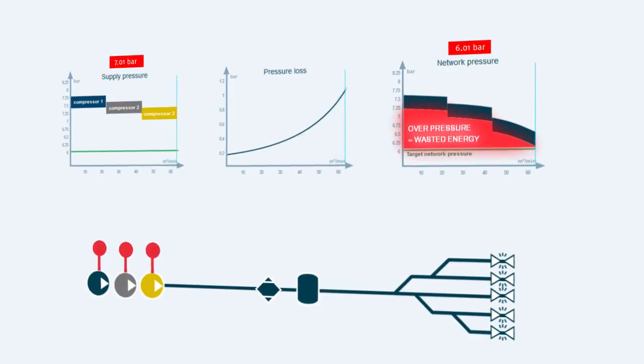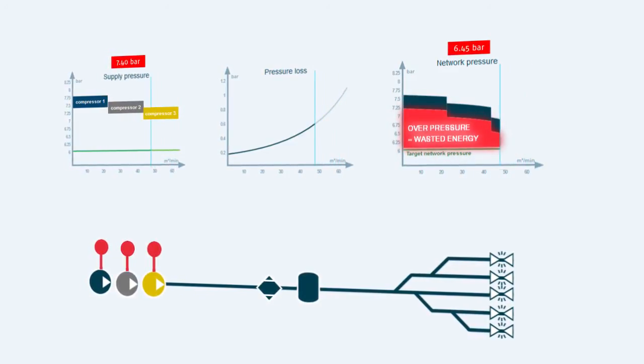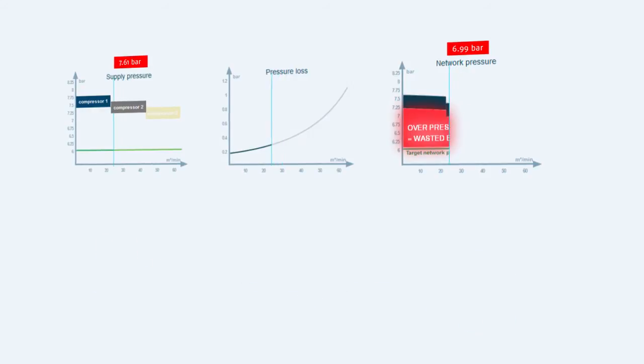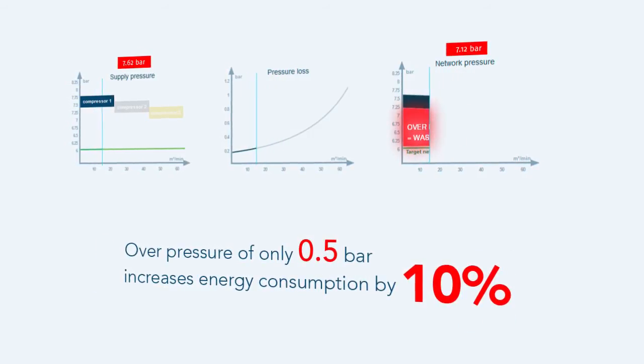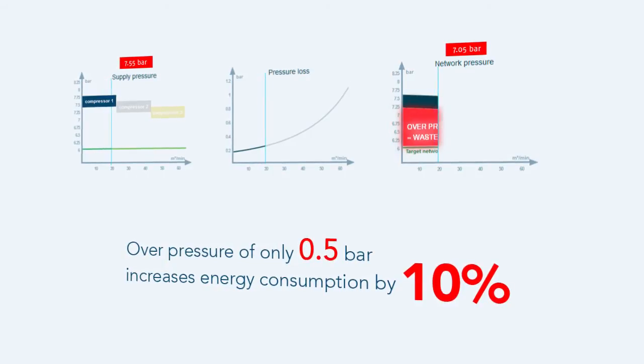If the required pressure level is, say, 6 bar, and the average system pressure is maintained at 6.5 bar, this extra 0.5 bar increases the energy consumption by 10%.